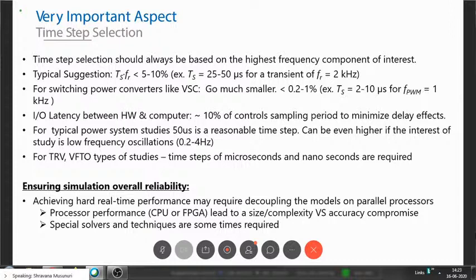Now, if there are switching converters, I suggest going much lower so that you don't miss the switching actions or switching events. If possible, try to go all the way to 1% of the highest frequency of the transient. So if you have, say, a 1 kilohertz PWM frequency, go to 2 microseconds, or you can play with up to 10 microseconds. The smaller you go, yes, the memory requirement will increase, sorry, but you can be sure that you will not miss any switching event if that is your region of interest.